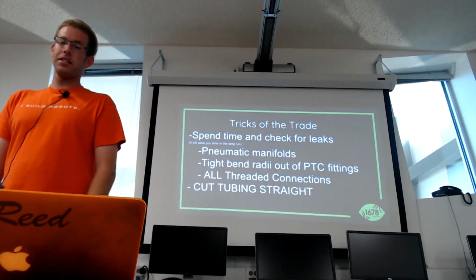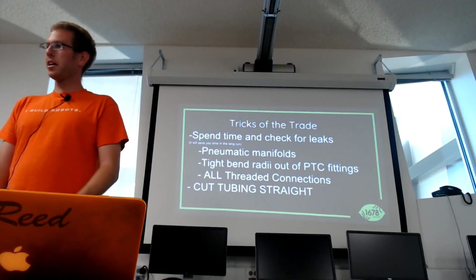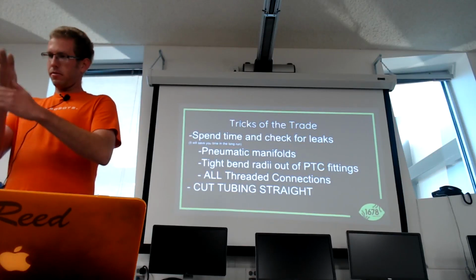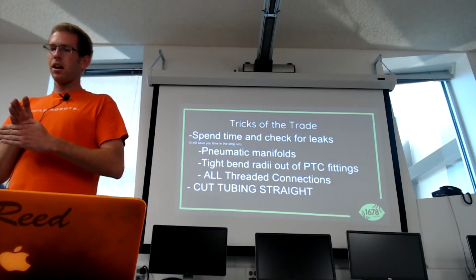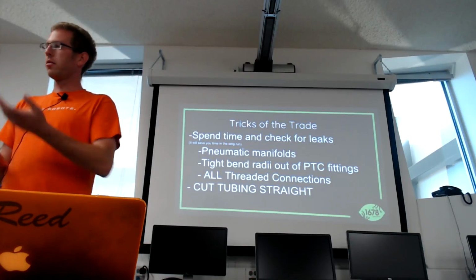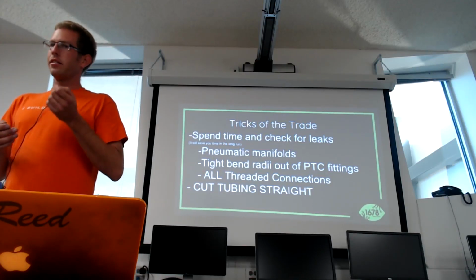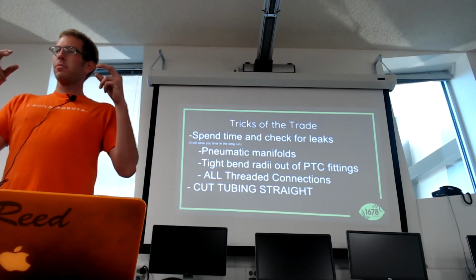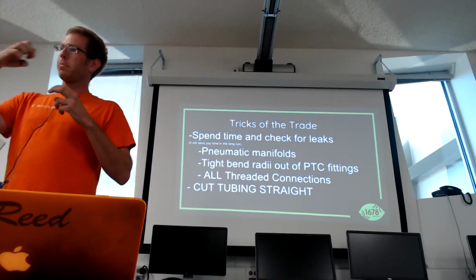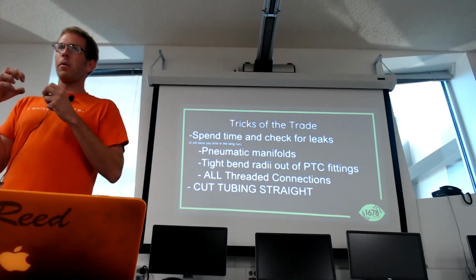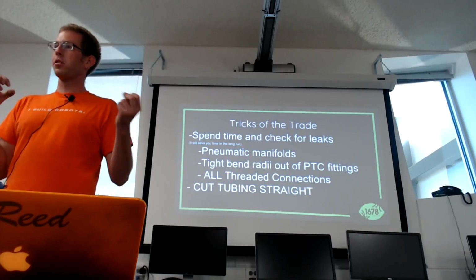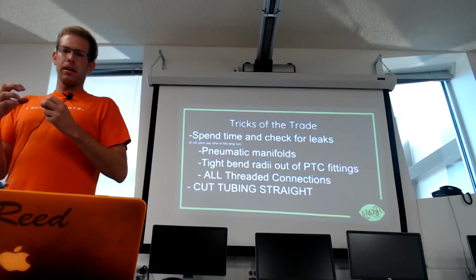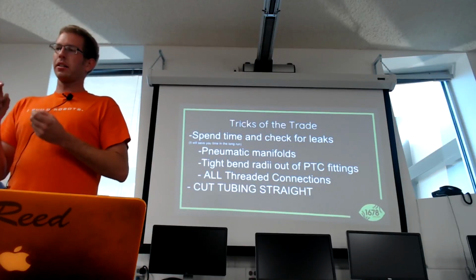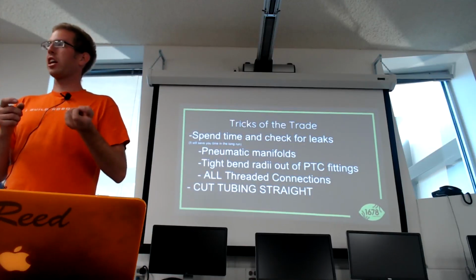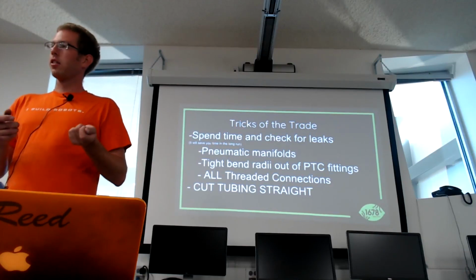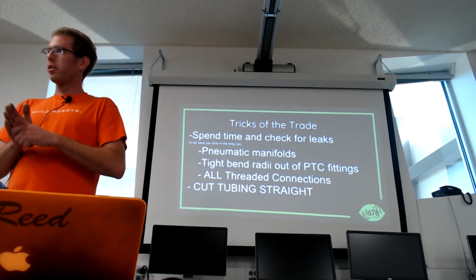The air will make the Windex bubble quickly so you can find your leak. Then cut the tubing straight at a 90-degree angle. A lot of people like to just use flush cutters or wire cutters, but that doesn't always let the alligator clips hold the tube all the way in, so it can blow off or leak. We actually use a tubing cutter from Automation Direct, I think it's about a dollar, and we'll use that to cut our pneumatic tubing to make sure it's nice and straight.